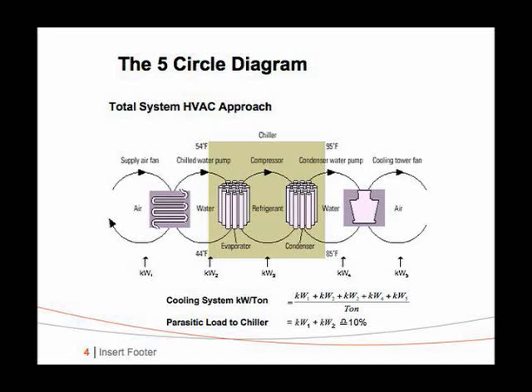And the pump needs kilowatts. You stuff that into a chiller, which has its own refrigerant loop, which also needs a kilowatt to drive the compressor. You dump that to a condensing unit, which also has water in it, typically for big plants. Again, we need the kilowatt. And then finally, you throw all this hot, humid air out to your neighbors. Hopefully not. And the fans, again, need kilowatts. So it's very useful to think of a system kilowatt per ton for HVAC, which is a sum of all the kilowatts divided by the tons that you have managed to remove from the first loop.